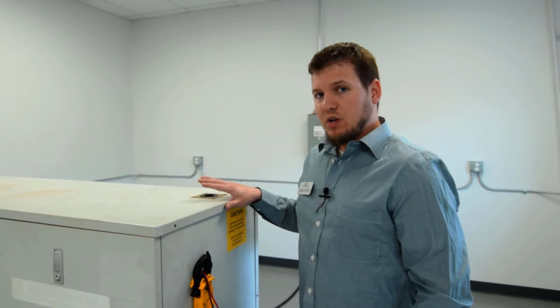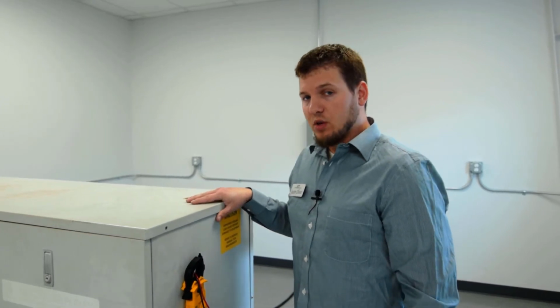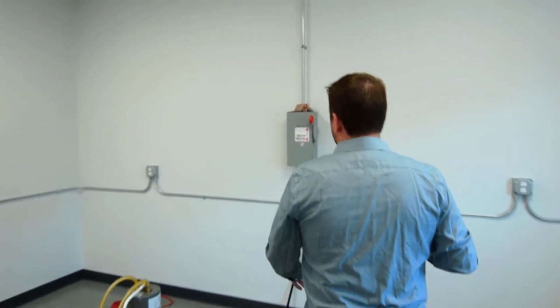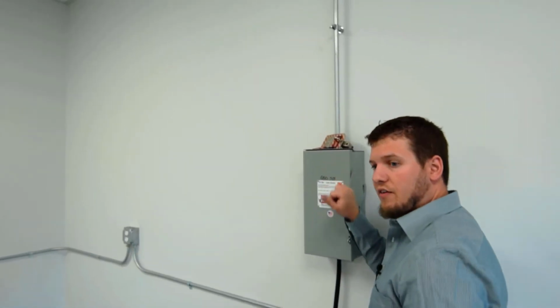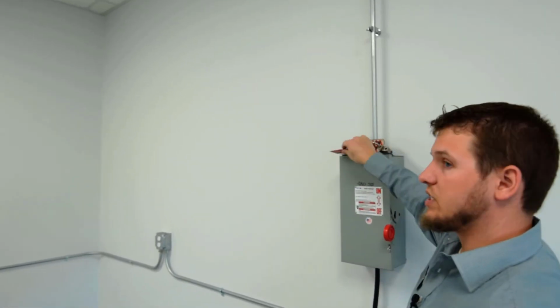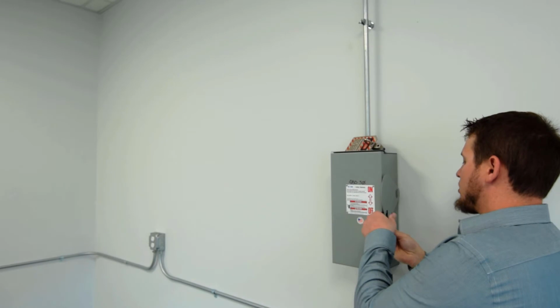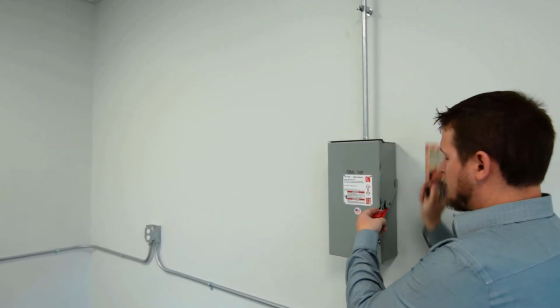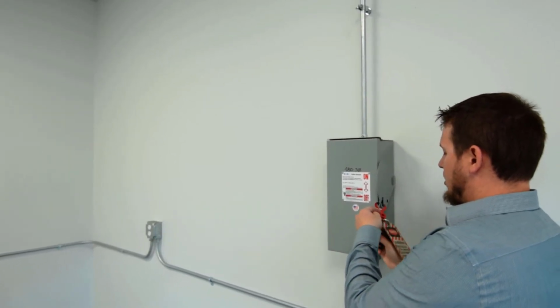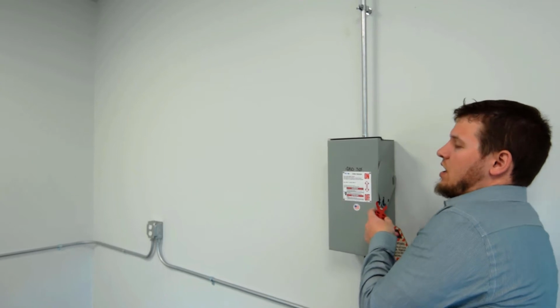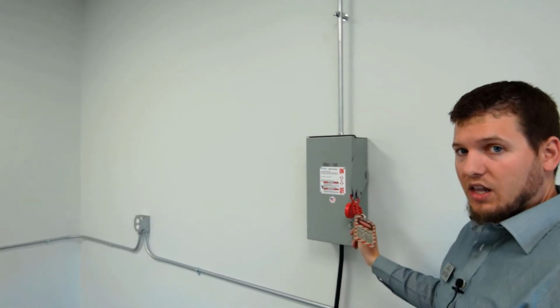The first step to do is to verify you have the power shut off to the unit. Here at ACT, we like to verify that the chiller is shut off at the main breaker located normally outside next to the chiller. And we also are implementing a lockout tagout sequence here. Please make sure that you're following the state laws and also your company policy on any kind of lockout tagout procedures.